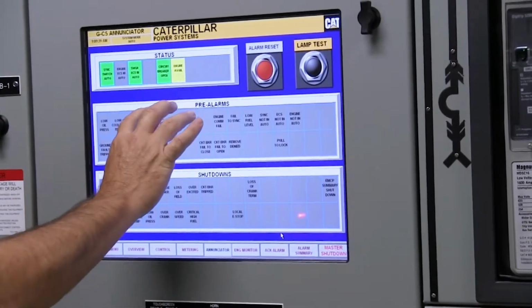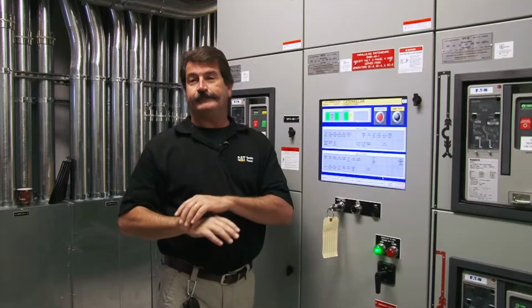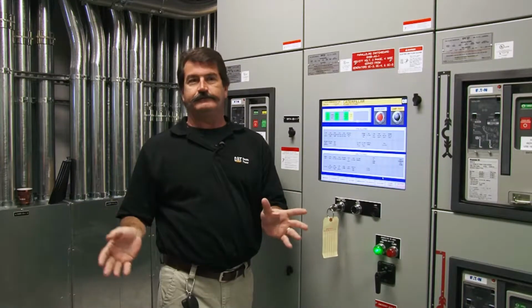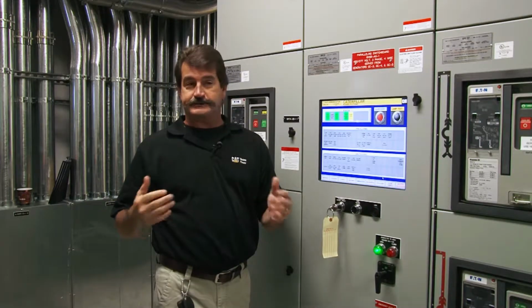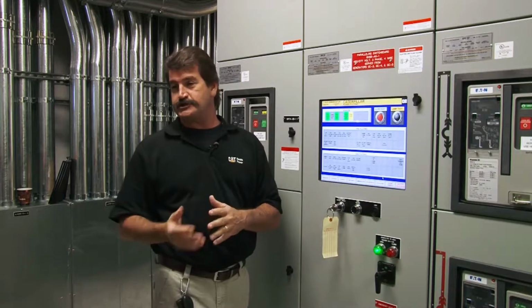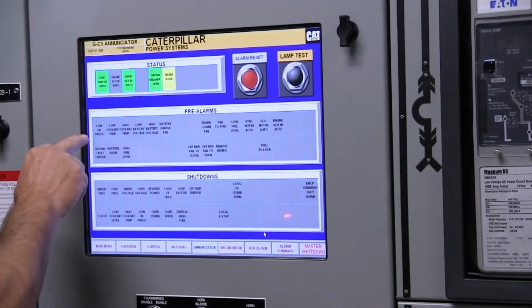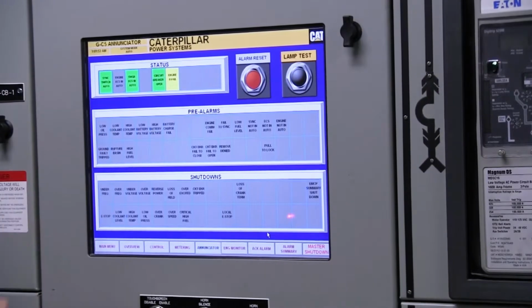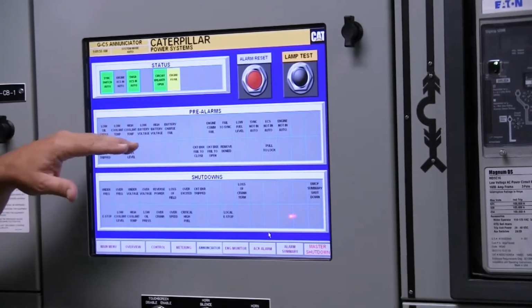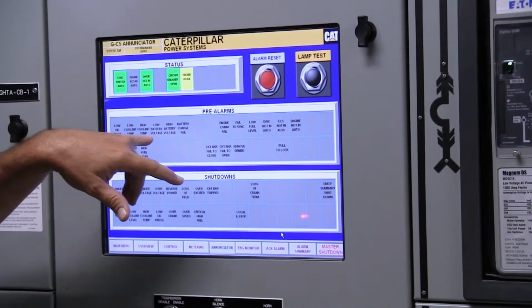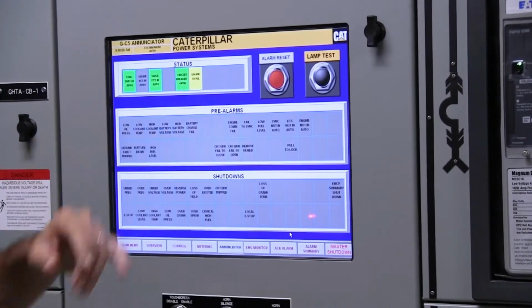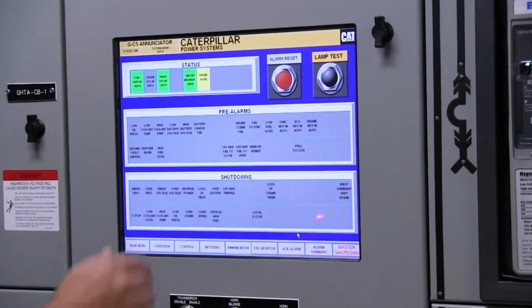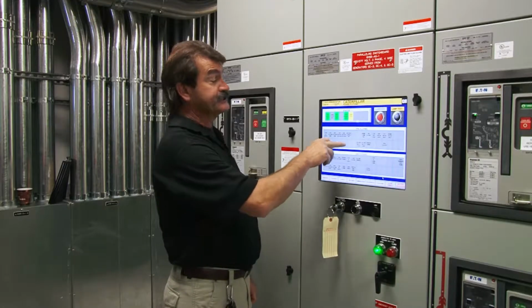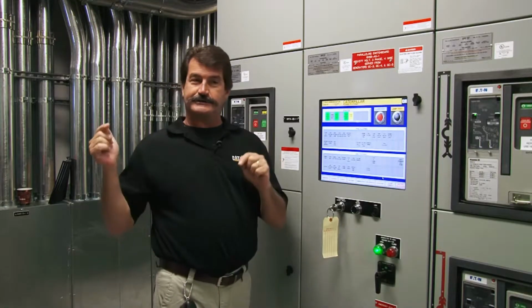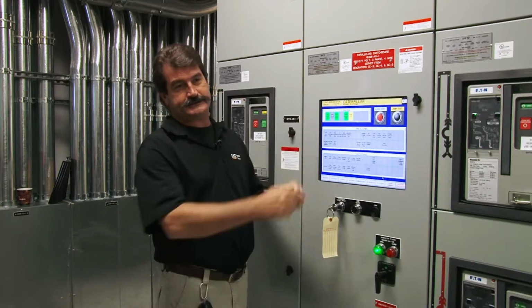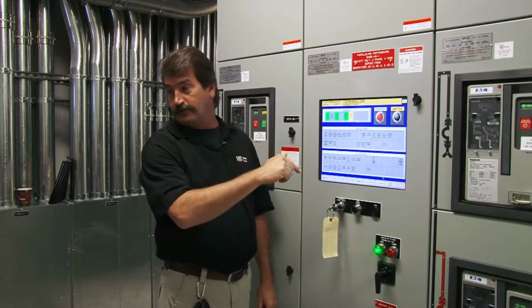So you got pre-alarms right here. They just alarm, just to let you know you've got a little problem. But it's not stopping the gen from starting up, and it's not shutting it down. These include any things that have to do with the engine, like oil pressure, coolant temp, stuff like that. Also battery voltage. Whenever we're talking battery voltage, that's the starter battery, the 24 volt starter battery. The reason we really care about that is because the starter batteries also supply us with backup 24 volt power.